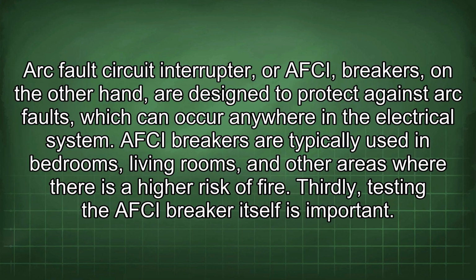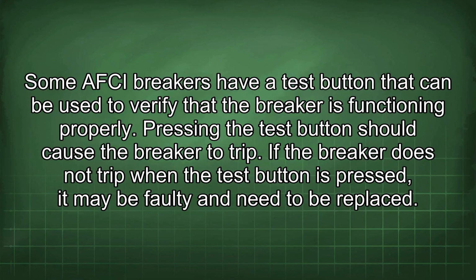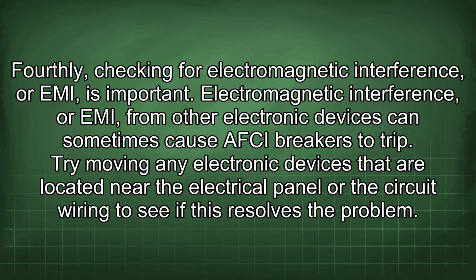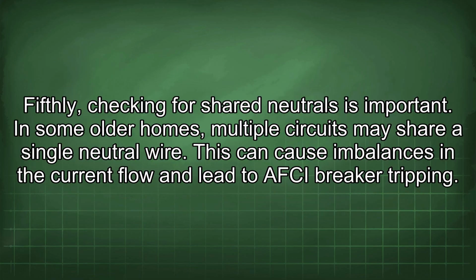Thirdly, testing the AFCI breaker itself is important. Some AFCI breakers have a test button that can be used to verify that the breaker is functioning properly. Pressing the test button should cause the breaker to trip. If the breaker does not trip when the test button is pressed, it may be faulty and need to be replaced. Fourthly, checking for electromagnetic interference, or EMI, is important. EMI from other electronic devices can sometimes cause AFCI breakers to trip. Try moving any electronic devices that are located near the electrical panel or the circuit wiring to see if this resolves the problem.